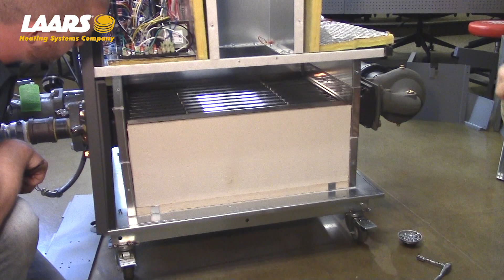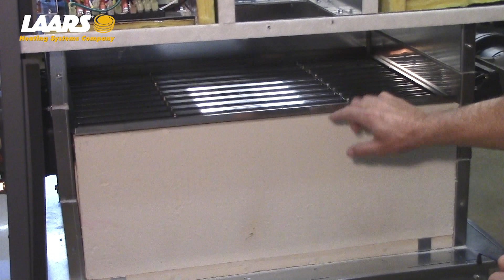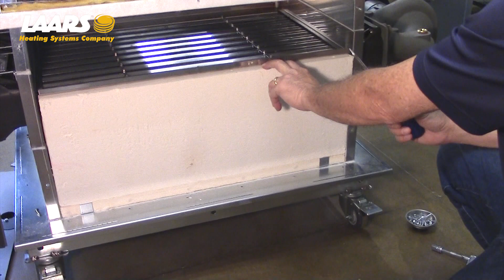So now what we have here is the back refractory block. You can inspect the top of the heat exchanger as well. If you are replacing this heat exchanger or pulling it out for cleaning, you may want to already order refractory tile to have on hand. In a lot of cases you will damage or break this. Also, anytime working with refractory material, you should be using a mask or respirator just in case you get the airborne type particles. On the smaller sizes, such as this is a 500,000, there's only one block.